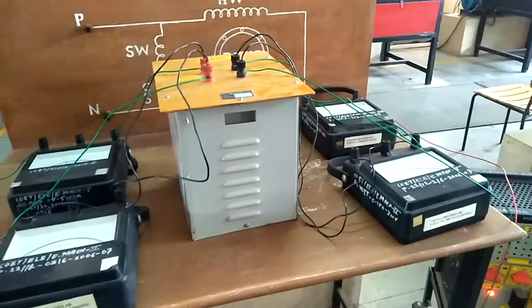This voltage ratio test and current ratio test can be applied in a similar way to the three-phase transformer, whether it is a distribution transformer or power transformer. The only difference is that we have to connect a three-phase supply for balanced three-phase voltage on the primary side, and a balanced three-phase load on the secondary side.